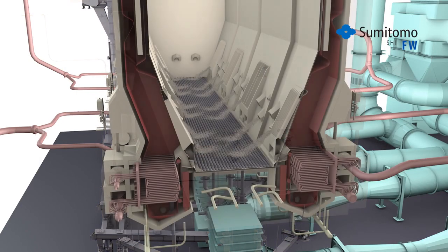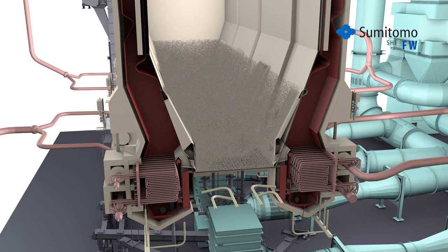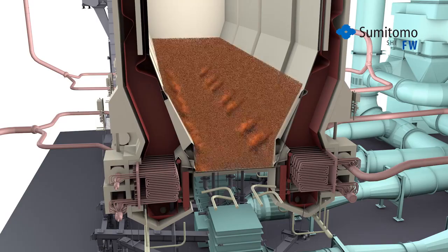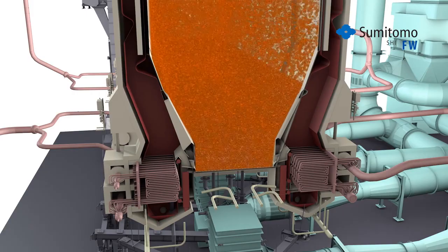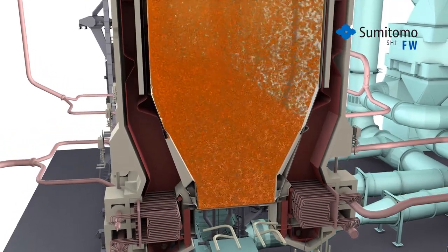Unlike conventional boilers that burn the fuel in a massive high-temperature flame, CFB technology utilizes circulating hot solids to cleanly and efficiently burn the fuel in a flameless combustion process.